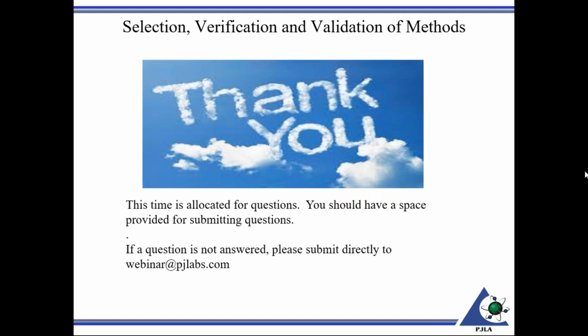If you go to a source that is accredited through an ILAC MRA, such as Perry Johnson Laboratory Accreditation, to perform the calibration, you get the accredited type calibration with calibration results. I can refer to that as a slam dunk. That would be considered a traceable measurement. So if traceability is needed, and you go to an accredited source and get the proper calibration, that would meet the requirement.